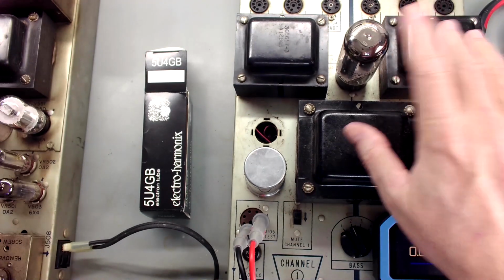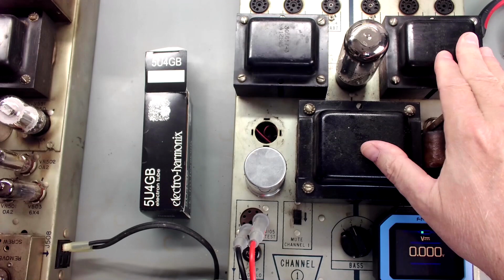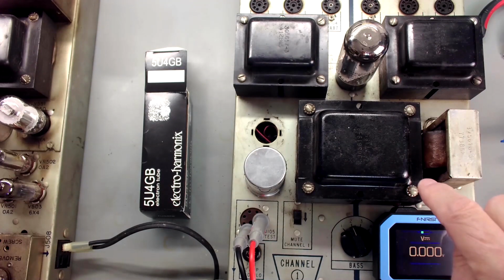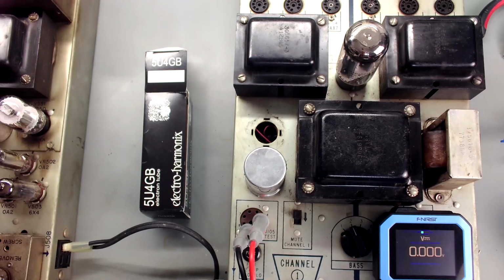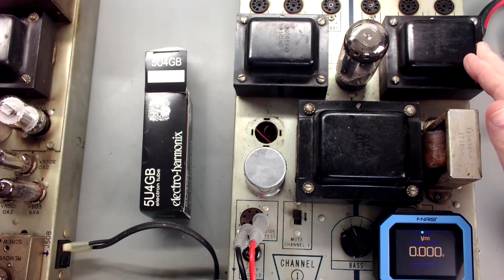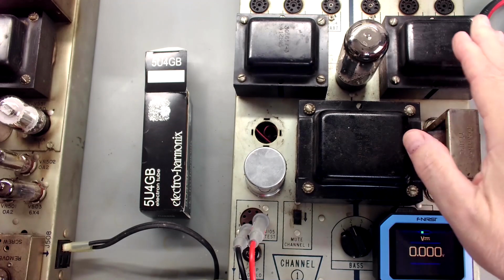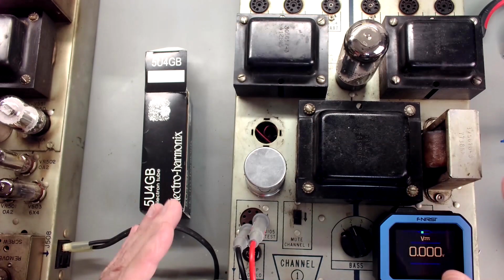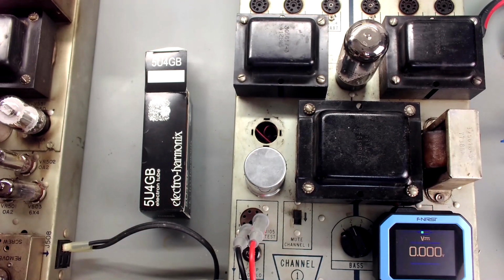Anyway, I went ahead and got a rectifier tube ordered. I put an ohm meter on all the windings, and they all appeared okay. I expected I'd have an open winding if there was a problem. This one and this one were pretty close in readings on each winding, so I felt confident they were okay.